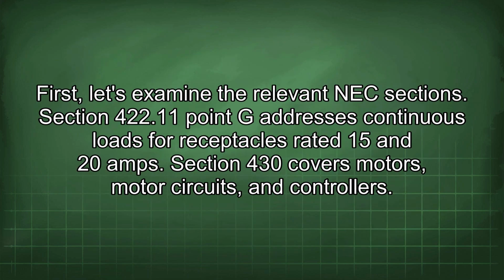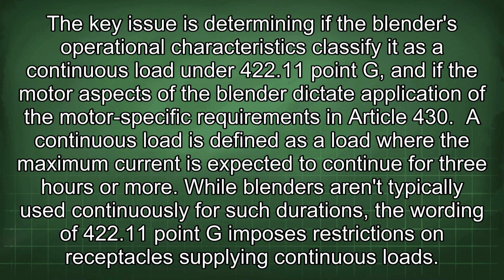First, let's examine the relevant NEC sections. Section 422.11.g addresses continuous loads for receptacles rated 15 and 20 amps. Section 430 covers motors, motor circuits, and controllers. The key issue is determining if the blender's operational characteristics classify it as a continuous load under 422.11.g, and if the motor aspects of the blender dictate application of the motor-specific requirements in Article 430.